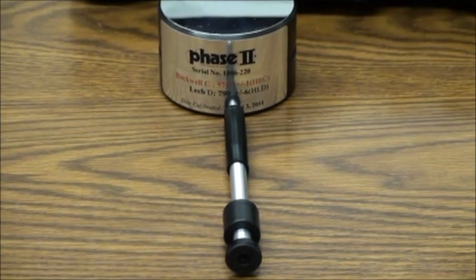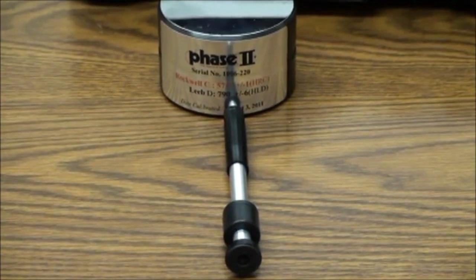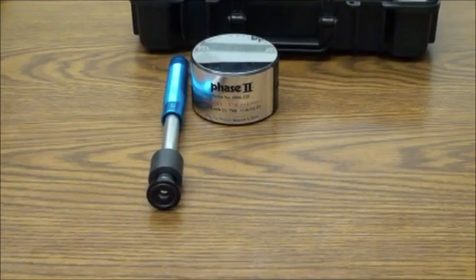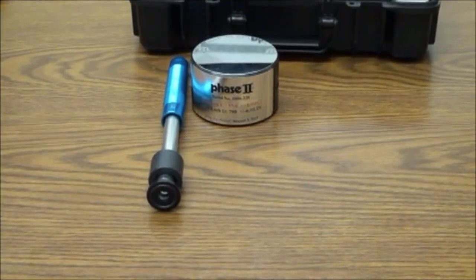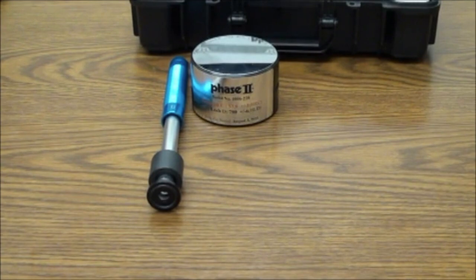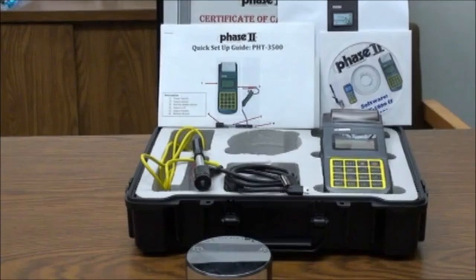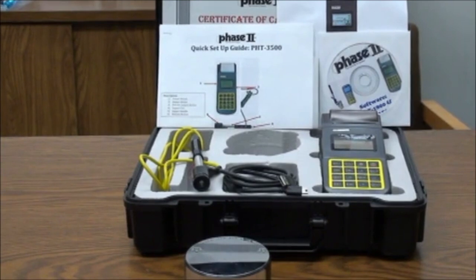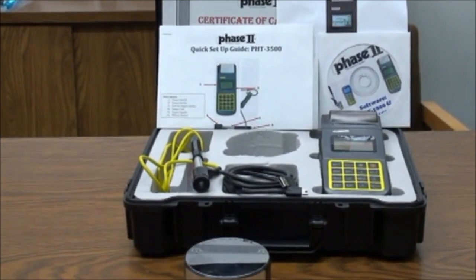The D15 probe has a narrow contact area for use in grooves or recessed areas. The G probe is designed specifically for rough surfaces or castings. It utilizes a 5mm ball, while all other impact devices use a 3mm ball. Now let's move over to the operation of the hardness tester and see how easy it is to utilize the different functions, taking tests, and obtaining results.